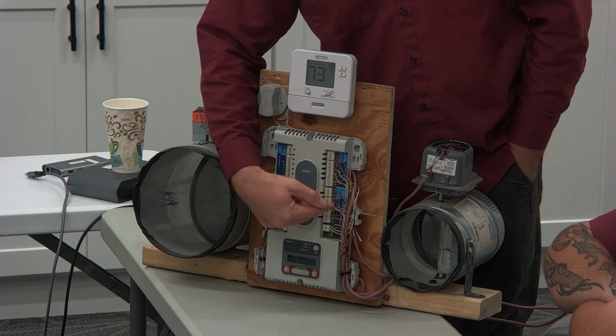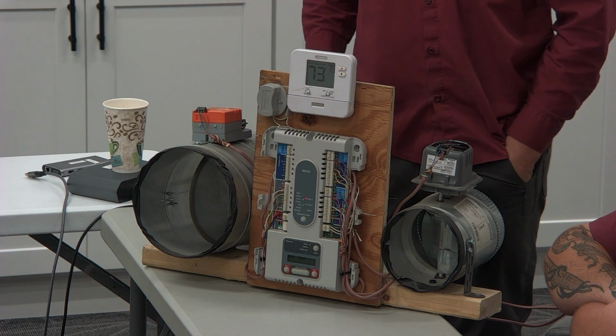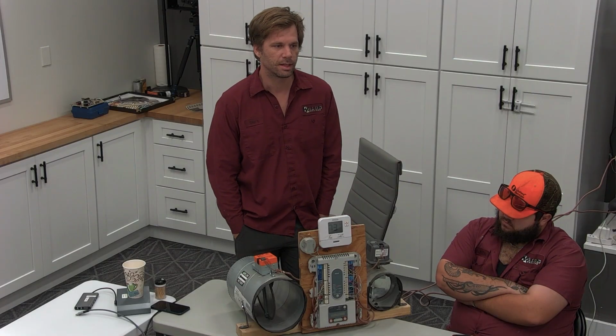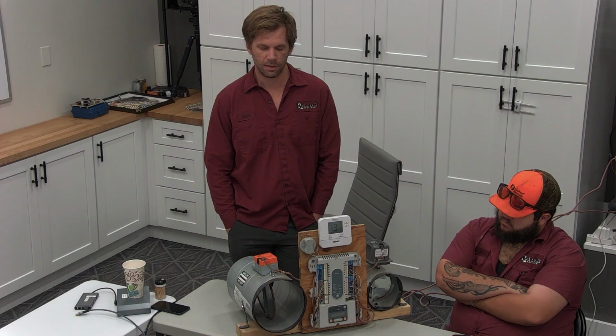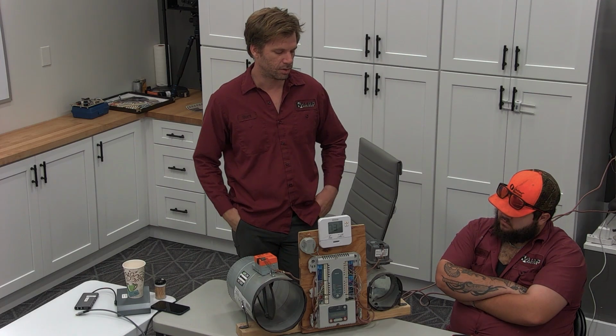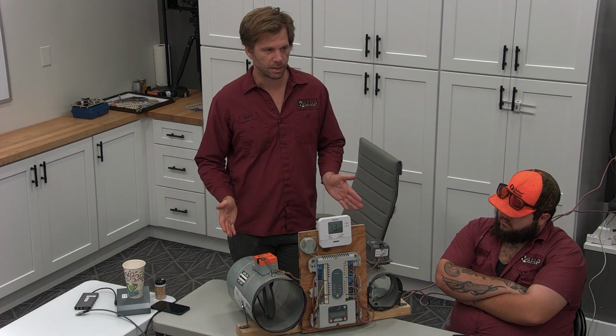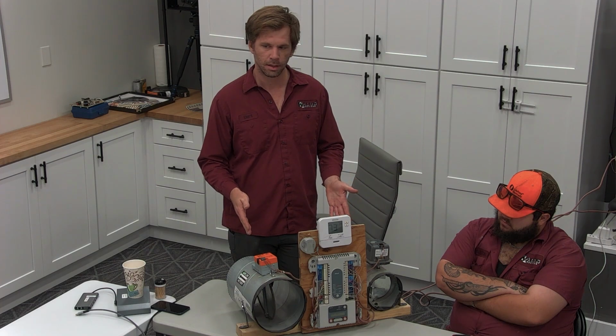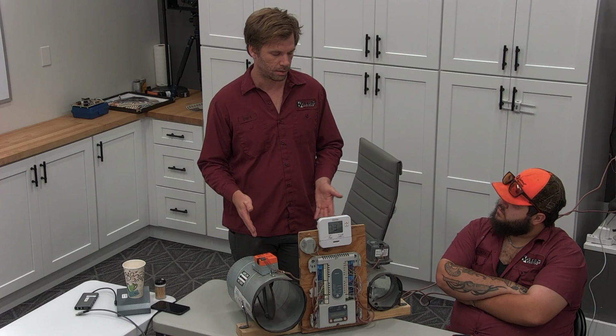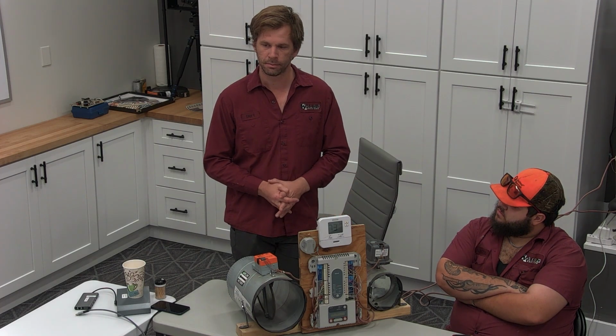Coming back, if it's not responding, finding out if we have voltage going to our motors on that zone. All of that can be done without going into the attic. Even if you're in the attic and you're looking at the motor turning, you don't even know if it's turning the damper. It could be loose on the damper shaft. Has anybody had that? Yeah, that's a tricky one.